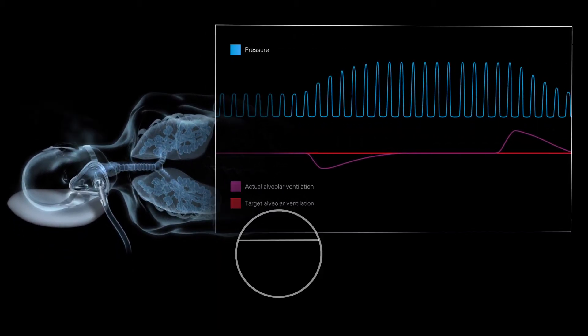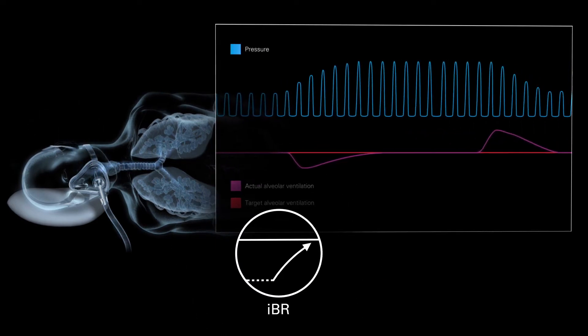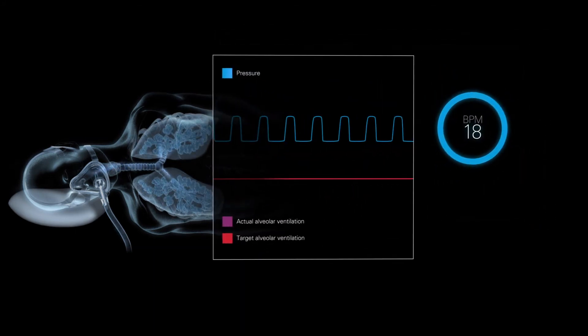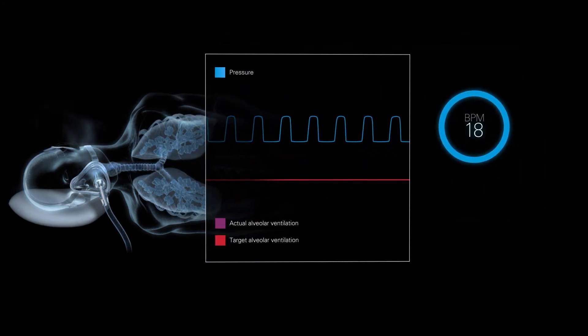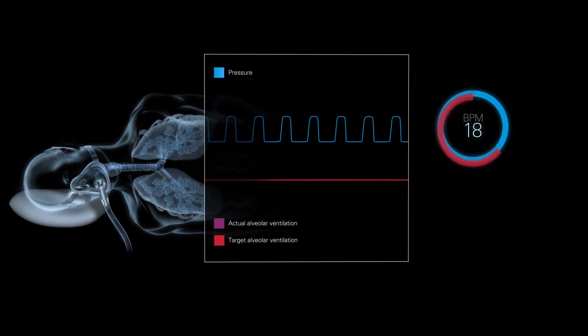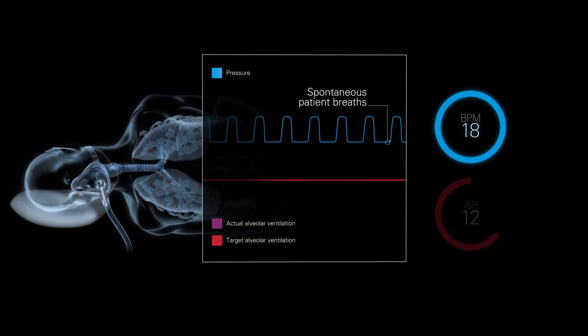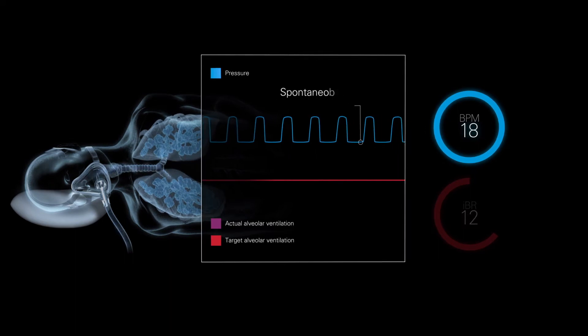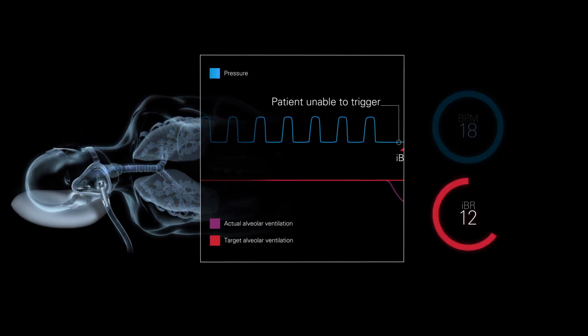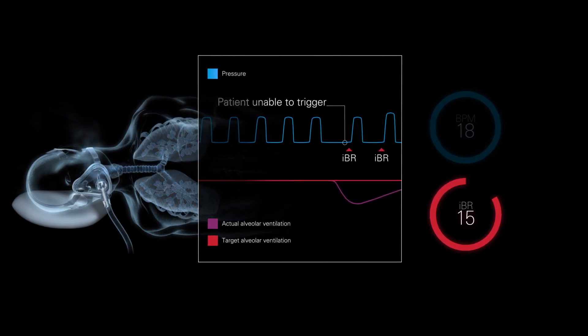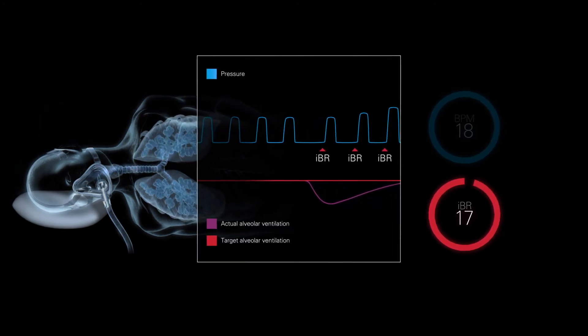Throughout this process, the Intelligent Backup Rate maximizes the patient's opportunity to breathe spontaneously. Generally, staying out of the way at two-thirds of the patient's spontaneous breathing rate, the IBR aids spontaneous triggering. If the patient is unable to trigger the device, the IBR provides backup breaths at the target patient rate to comfortably bring them back to target.